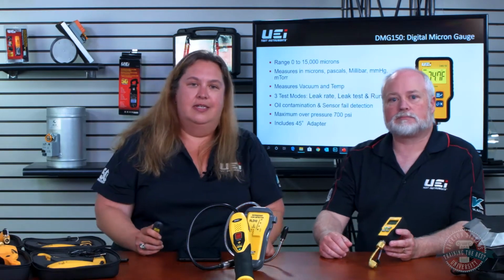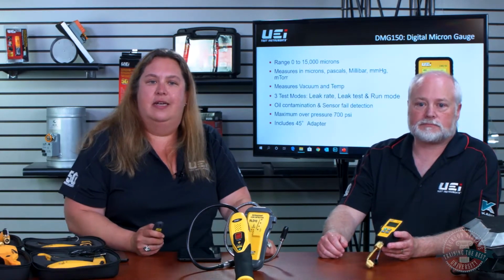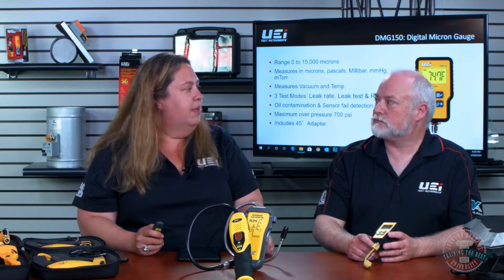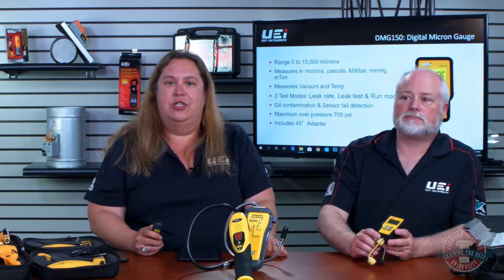All right. Well, one of the things that I've definitely heard is that the sensor gets contaminated. And what do you do when the sensor gets contaminated, I think, is a really important thing, because you can clean the Micron Gauge. And that's something that I do want to touch base with tonight. So if you notice, Mark's holding up our Micron Gauge, and it has that nice 45-degree coupler attached to it.